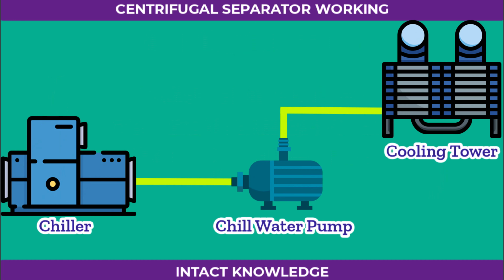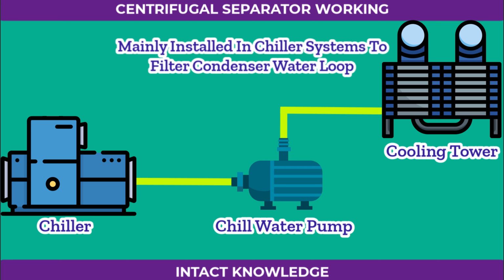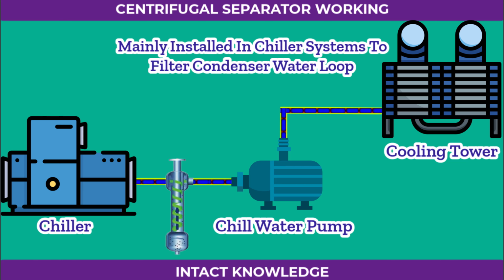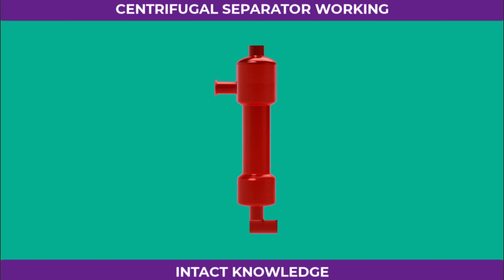These separators are mainly installed in chiller systems to clean the condenser water loop. The condenser pump draws water from the cooling tower and sends it toward the chiller. Before that water enters the chiller, it first passes through the centrifugal separator, then continues onto the chiller itself. Now, let's see how this device functions. But before that, let's go over its main components.